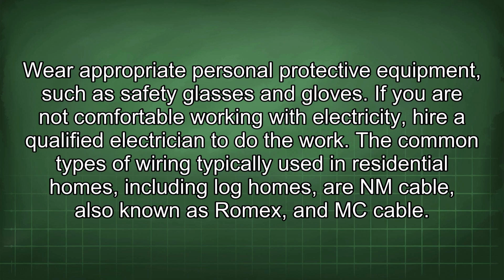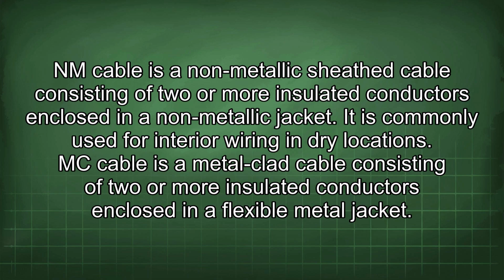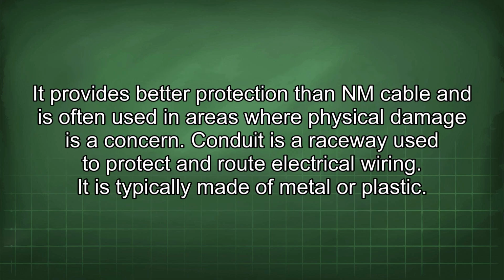The common types of wiring typically used in residential homes, including log homes, are NM cable, also known as Romex, and MC cable. NM cable is a non-metallic sheathed cable consisting of 2 or more insulated conductors enclosed in a non-metallic jacket. It is commonly used for interior wiring in dry locations. MC cable is a metal-clad cable consisting of two or more insulated conductors enclosed in a flexible metal jacket. It provides better protection than NM cable and is often used in areas where physical damage is a concern.